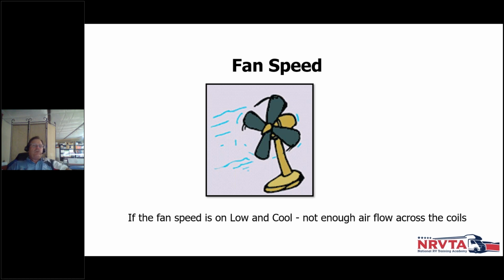Another thing we run into is the fans. A lot of people like to run their fans on low cool. In other words, you can run an air conditioner fan on low fan, which means it's just going to be blowing air, or you can run low cool. Cool means you're going to run the compressor. But here's the thing, when you run it on low fan speed, it doesn't move enough air across the coils to keep the airflow going through there.